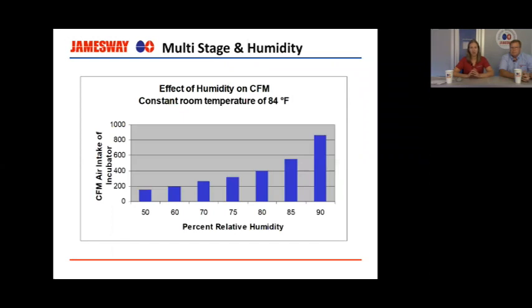This is some data on a multi-stage machine. So based on the percent relative humidity in the room, this is how much fresh air that multi-stage machine wants. Because remember, they're 100% air cooled. So at 50% humidity in this test, they were below 200 CFM. By the time the room hit 80%, we doubled to 400 CFM. And at 90%, we're at 850 CFM. So that's why humidity is so important, because it really is going to change, especially in your multi-stage machines, how your machine is going to react. Also very important in your platinums.